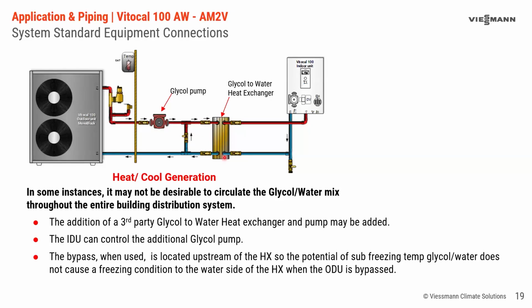That's fine, it's not going to freeze, but the water that's in this plate is just going to be boiler water, just treated system water, and we don't want this to freeze. So to solve that problem, we put the bypass on the glycol side, so that way the bypass is here, and we always have the boiler water or the system water, whatever, traveling through this side. Okay, so that's an important thing to remember if you're going to be putting a heat exchanger in and you want a bypass for servicing and that kind of thing, that you put the bypass on the glycol side.